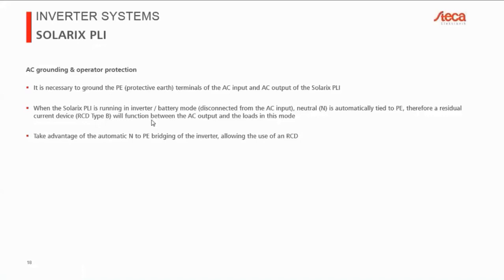And what's interesting is if you've ever looked at residual current devices, you'll know that they only work if there's a working ground connection. So typically the PE is connected to the neutral. This typically happens either in your home or maybe already at the electricity provider. But at some point there's typically a bridge between the neutral and ground. And this bridge is before the AC input of your SOLARIX PLI. Now, if your SOLARIX PLI is working in off-grid mode, it disconnects both the live wire and the neutral wire from your AC source. And in this case, your neutral would be what's called floating.